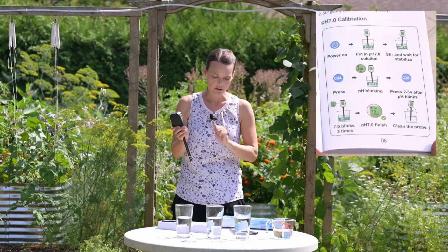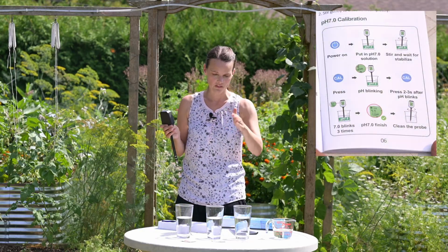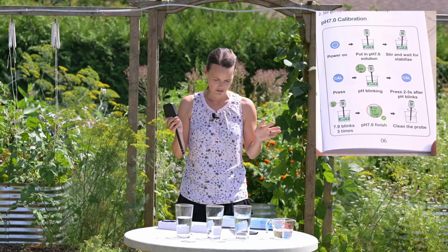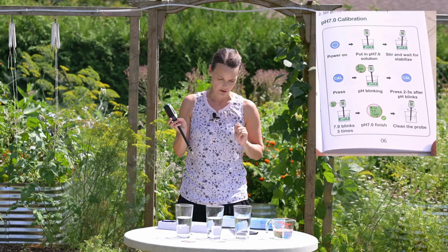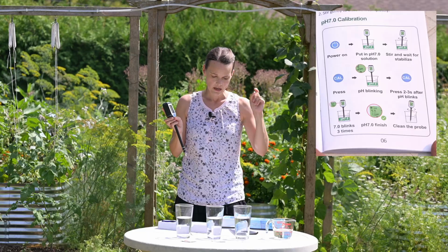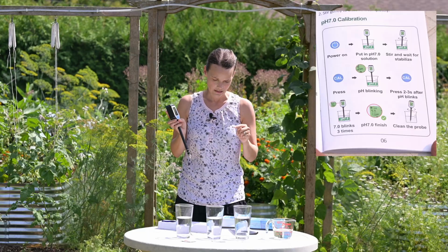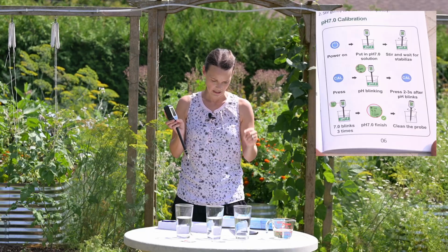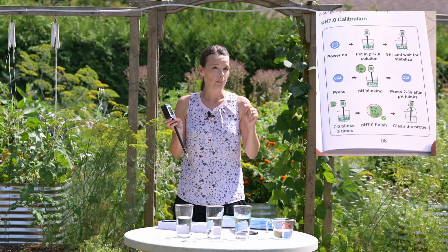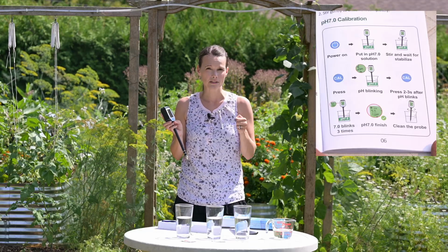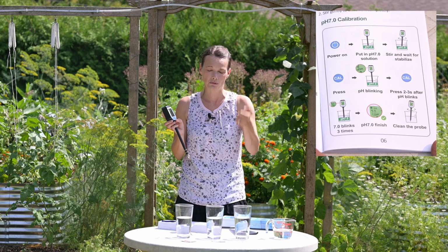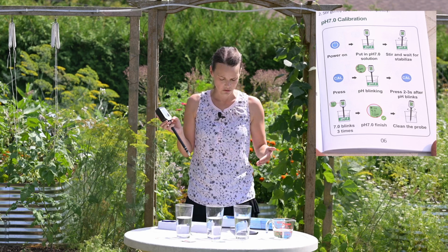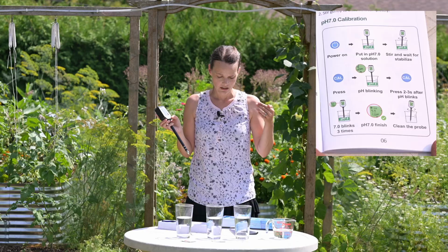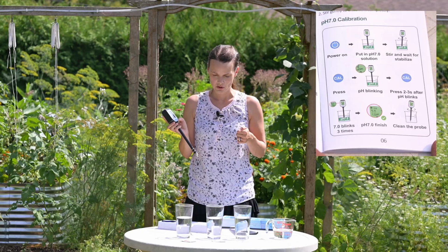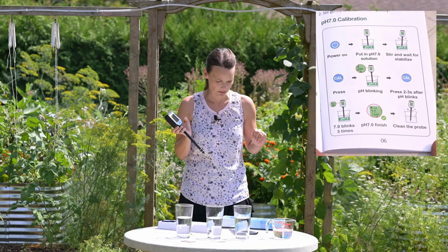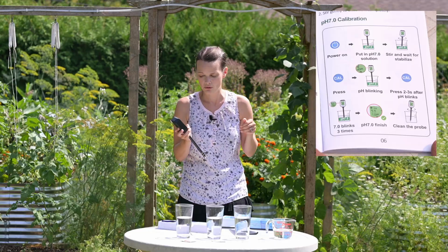It says power on, put it in the pH 7 solution. This one, stir and wait for stabilize. Press calibrate, pH blinks. Press 2 to 3 seconds after pH blinks. I wonder if it means 2 to 3 times after the pH is blinking, go 1, 2, 3. And then the 7.0 should blink 3 times, and then it should finish, and you clean the probe. I did clean the probe again in between. Let's try it with pressing it 2 to 3 times.